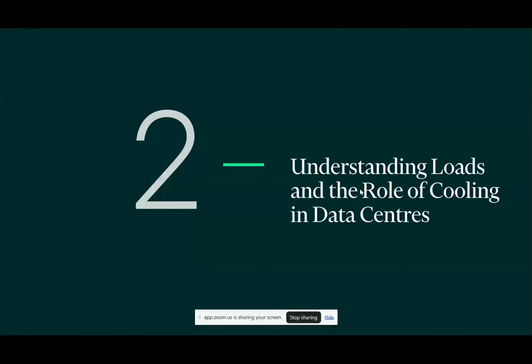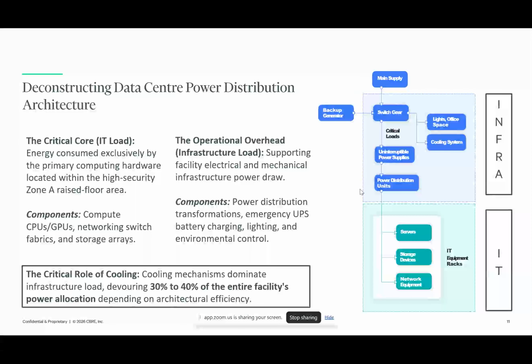We've heard earlier speakers talk about the loads and potential opportunities, so let's quickly go through the key elements and then talk about emissions. In a data center, you've got the infrastructural load and the IT load. The critical core is the IT load, where energy is consumed exclusively by computing hardware, including GPUs, networking switches, storage arrays, and so on. Then there's the infrastructure load, which covers the electrical and mechanical infrastructure supporting the IT load, including transformers, UPSs, lighting, environmental control, and battery charging. The key thing to remember is cooling mechanisms dominate the infrastructure load, accounting for around 30 to 40% of the entire facility's power allocation.